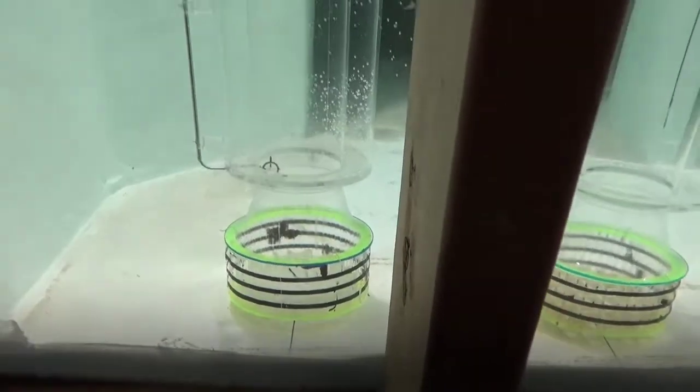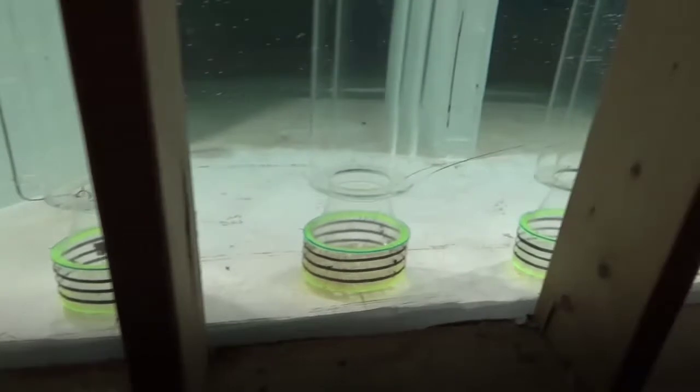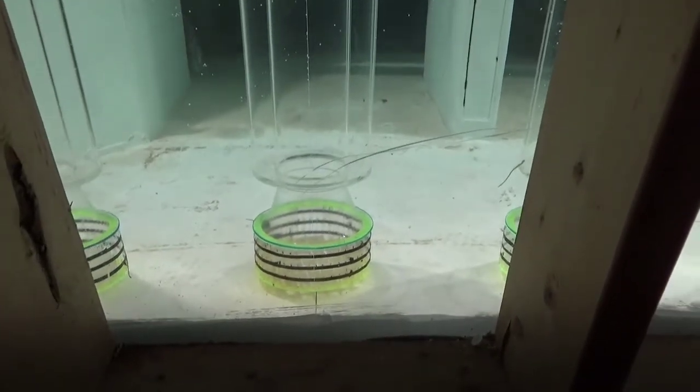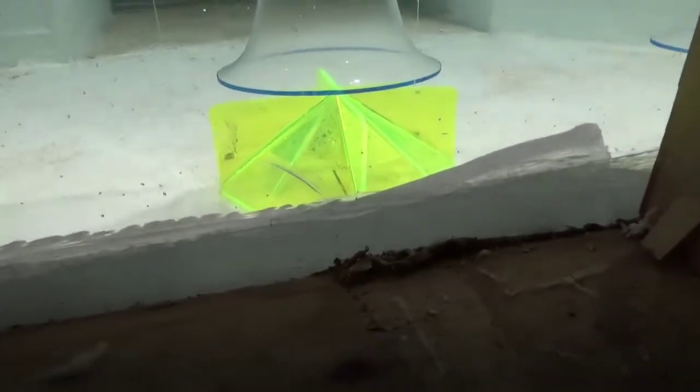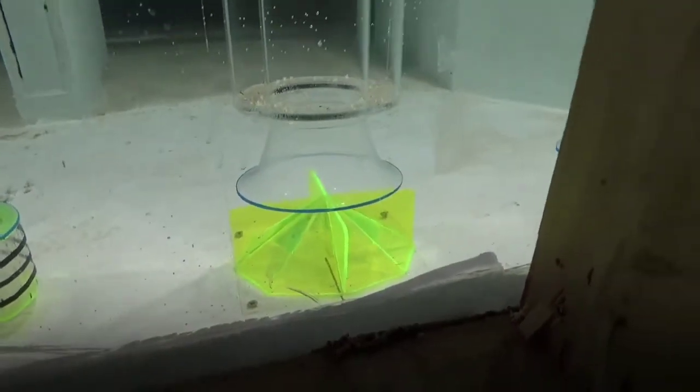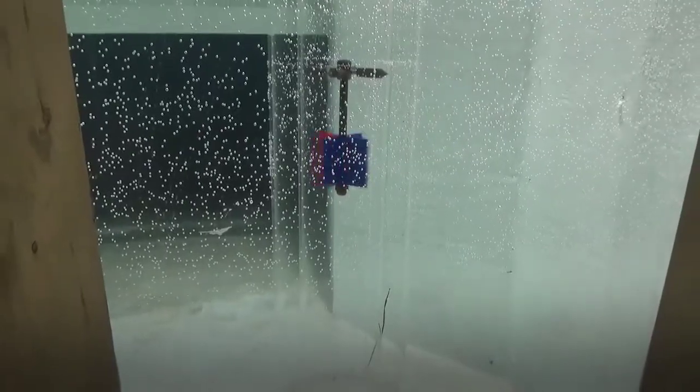They can be installed in the dry outside of the wet well, or they could be attached to the floor. That detail can be sorted out. We're going to recommend attaching to the pump here. We've also looked at a floor cone, which would bolt to the floor. It's not as effective, and over here we have nothing. So as we saw in the baseline video, really high pre-swirl right here. Over here, if you'll notice, it still has pre-swirl.